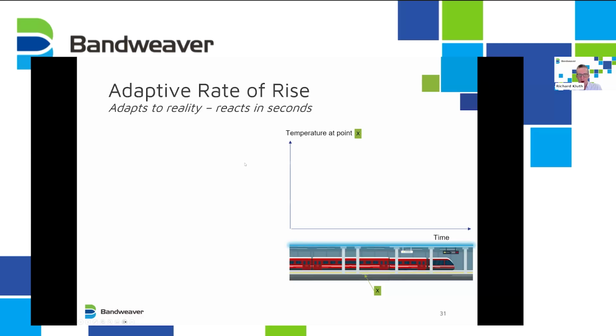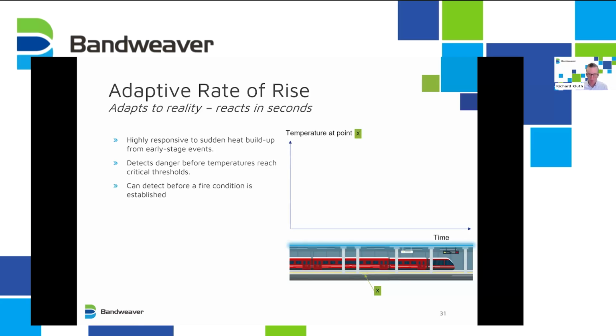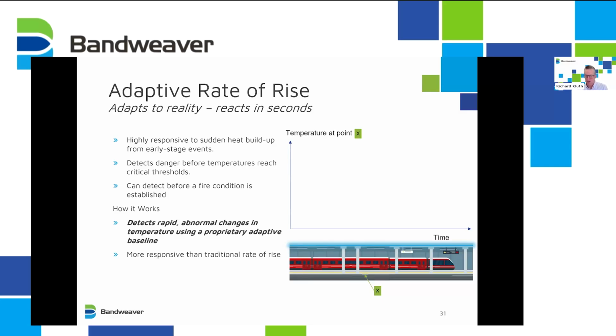The second one is the adaptive rate of rise. This is very responsive to sudden heat build-up in very early stage events, before you reach any critical thresholds, even before a fire condition is established. In some of our examples, we'll see you can have heat and still no flame, so a flame detector or smoke detector wouldn't detect this because there's only heat present. So how does it work? It detects rapid changes, abnormal, something not normal, changes from the baseline. It's constantly monitoring the baseline and making measurements of changes from that. So it's more responsive than a conventional rate of rise, and optimized to minimize false alarms.